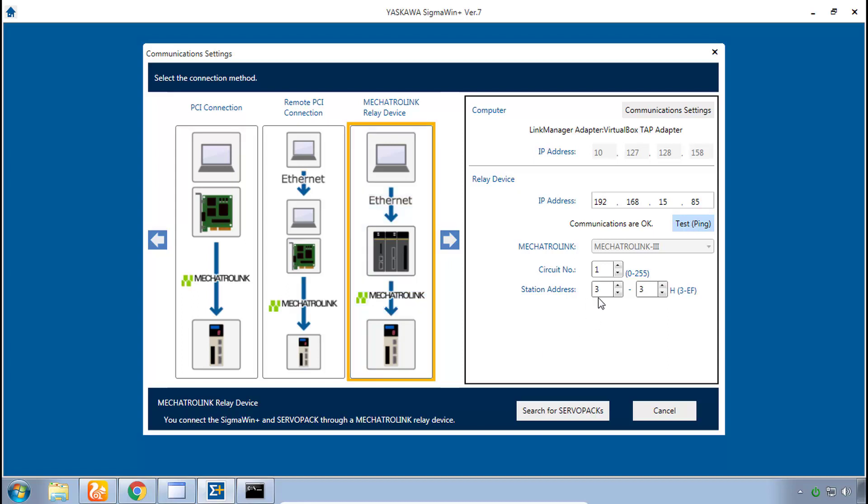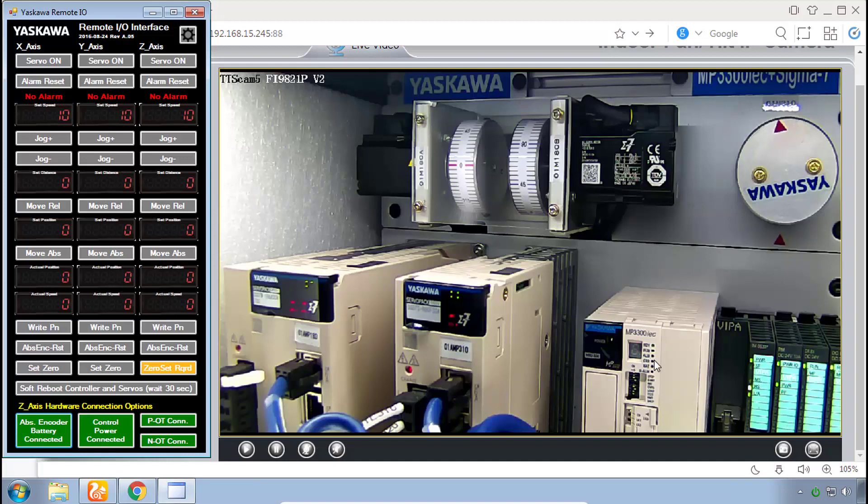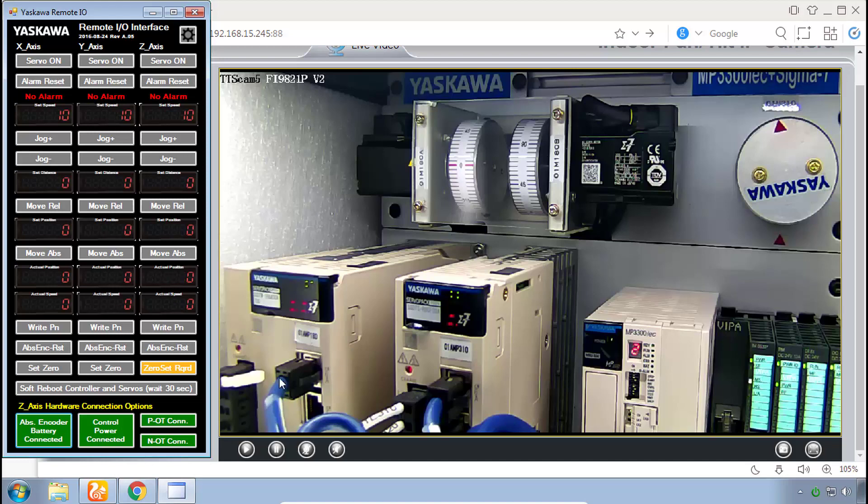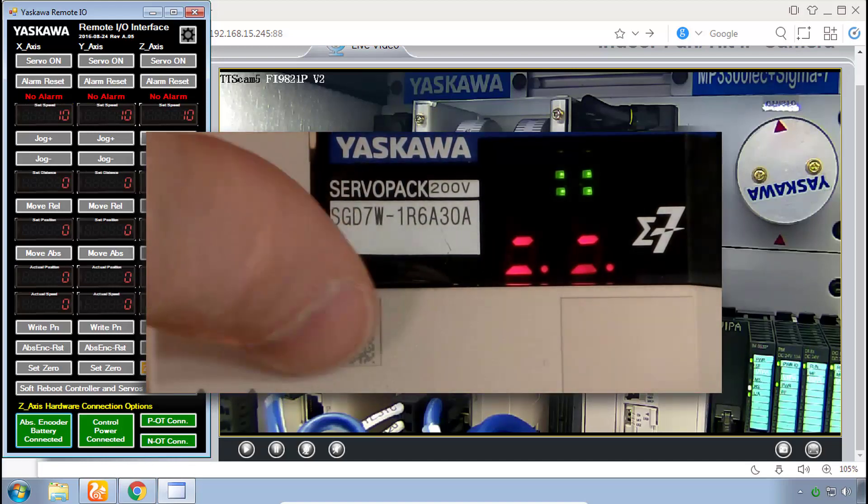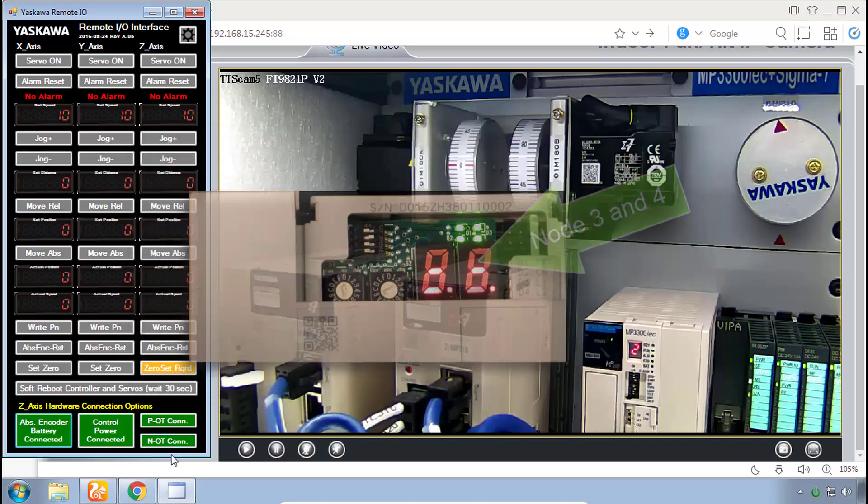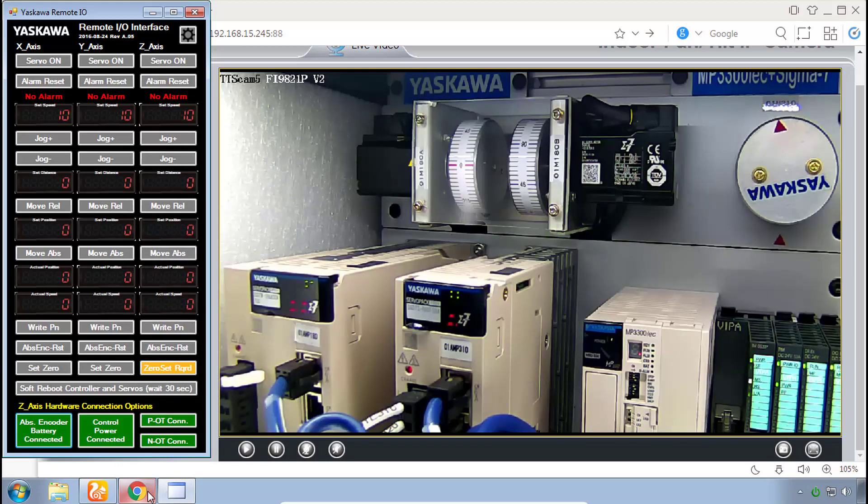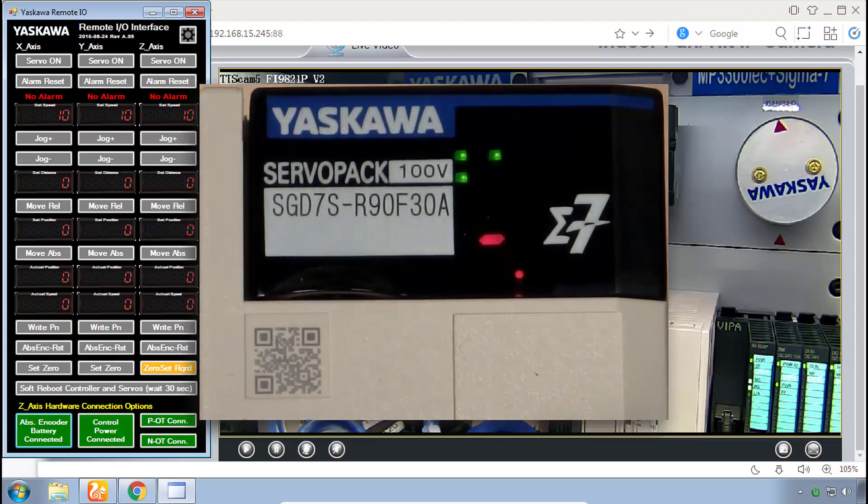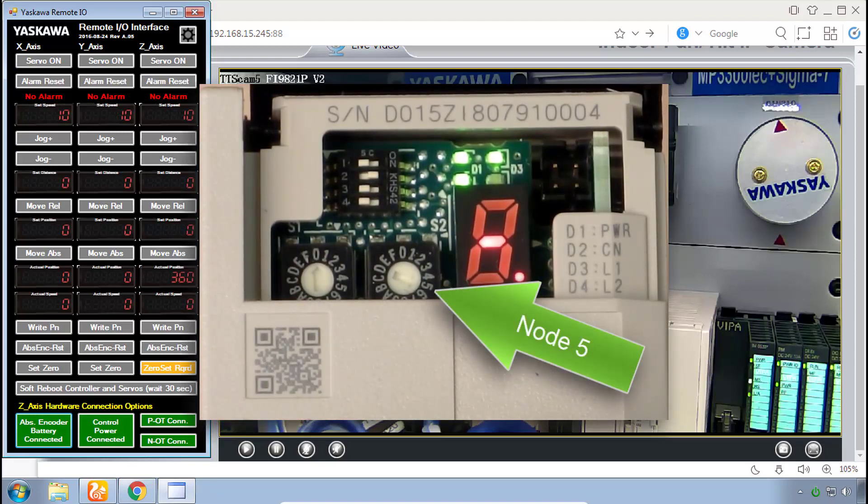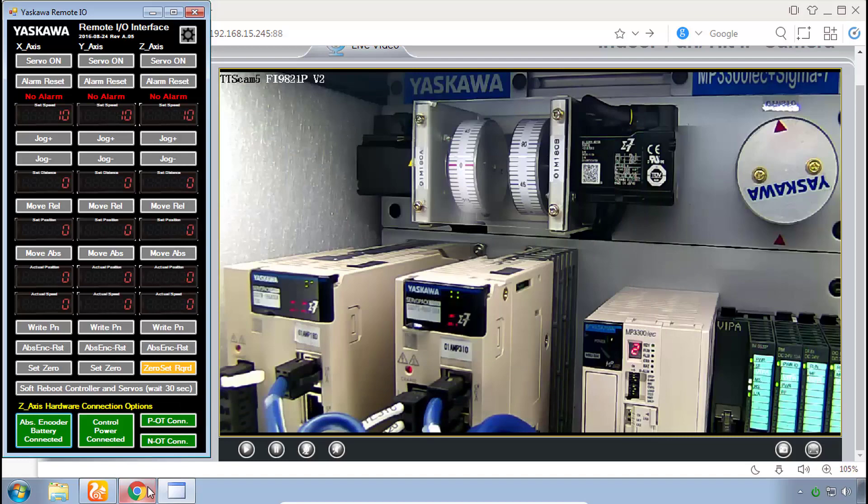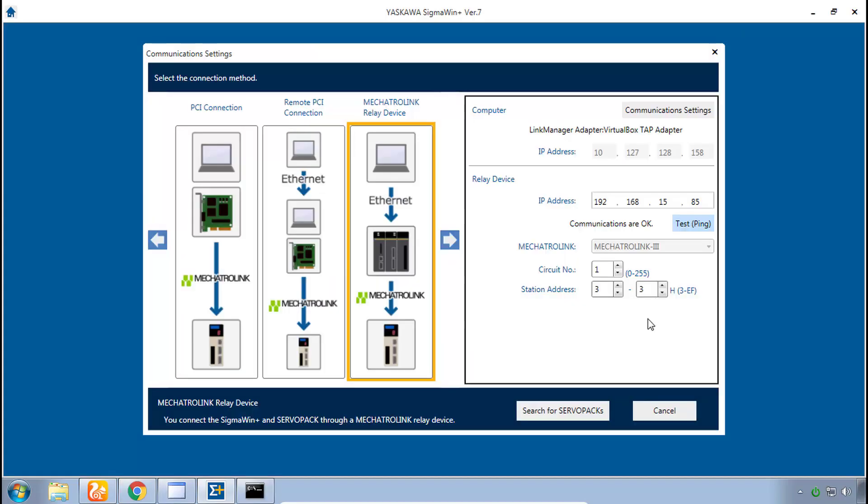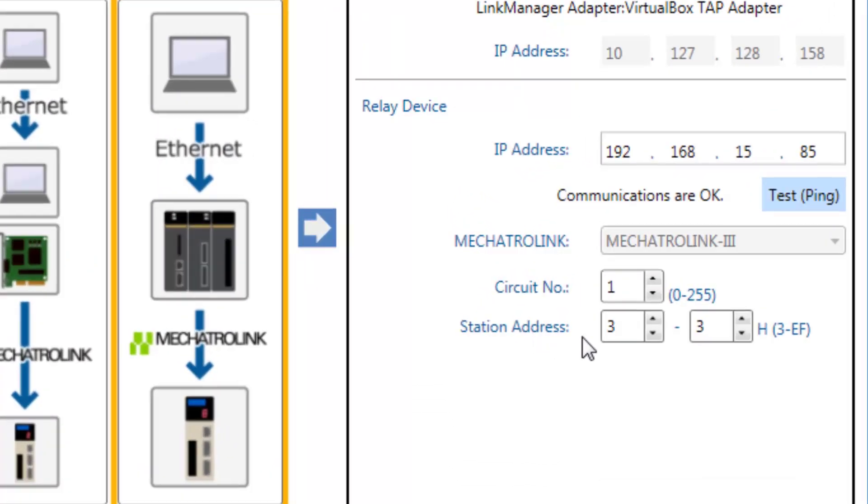And that is the station address of the connected servos. Both of the servos are networked over Mechatrolink 3 to the MP3300 IEC controller. The dual axis amplifier is set for network nodes 3 and 4 while the single axis amplifier is set to node 5. Therefore we will set the station address here as starting at 3 and ending at 5.